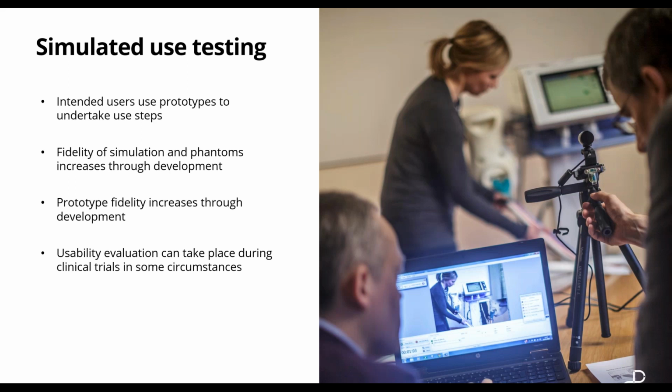With very medically invasive products, it is also possible to undertake usability evaluation as part of a clinical trial, because sometimes it really is only through having an actual person or intended patient there that you can check the usability of a product. However, most of the time, this can be done as simulated use testing in a small room with nothing more than the product and the discussion.